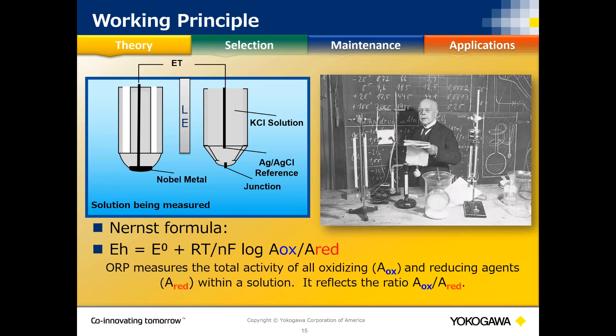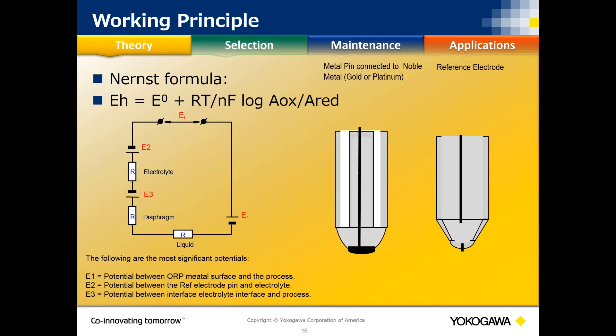The silver-silver chloride pin is immersed in a KCl solution with a junction open to the process — that combination provides a zero millivolt reference value. This allows us to read just the millivolt value generated on that noble metal and get the actual ORP reading.